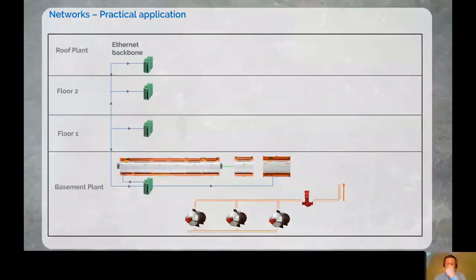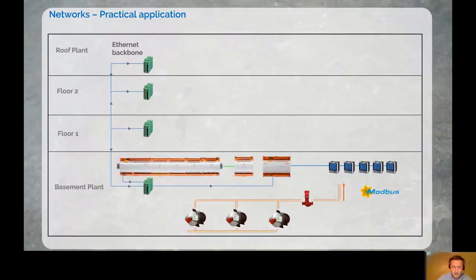We'll also include at this stage, the first time we've talked about this, a Modbus interface. The real good thing about Modbus, and protocols in general, is that most vendors nowadays come with third-party integration capability. This means the end user isn't vendor locked. So if a specific vendor, in this case Trend, or anyone else, it doesn't mean you have to just use Trend products - you can use other third-party products. From a pricing perspective, it allows a lot more choice, so it's really good that we get this. In this case, it's Modbus.